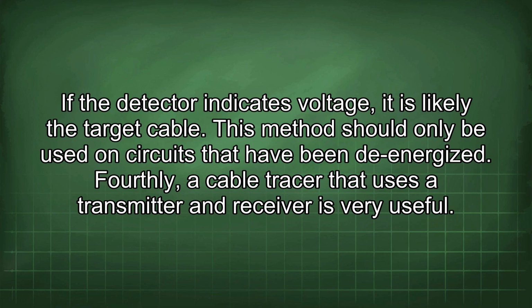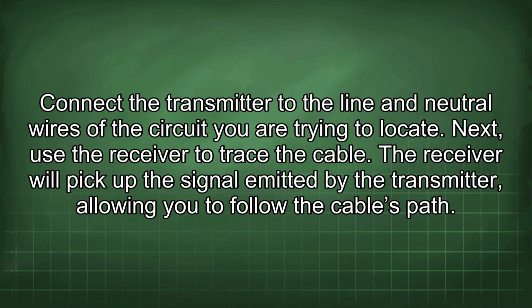Fourthly, a cable tracer that uses a transmitter and receiver is very useful. Connect the transmitter to the line and neutral wires of the circuit you are trying to locate. Next, use the receiver to trace the cable. The receiver will pick up the signal emitted by the transmitter, allowing you to follow the cable's path.